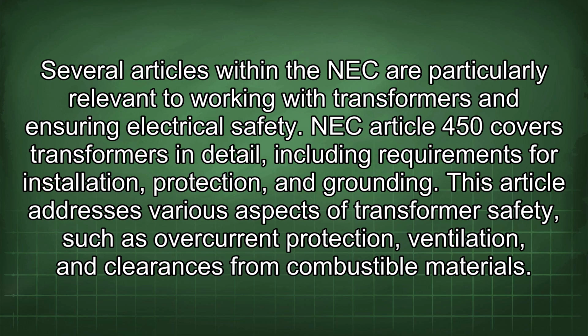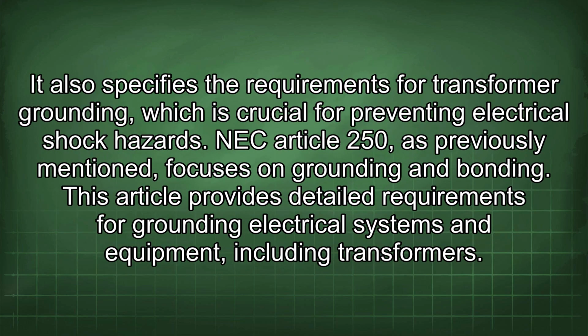NEC Article 450 covers transformers in detail, including requirements for installation, protection, and grounding. This article addresses various aspects of transformer safety, such as overcurrent protection, ventilation, and clearances from combustible materials. It also specifies the requirements for transformer grounding, which is crucial for preventing electrical shock hazards.